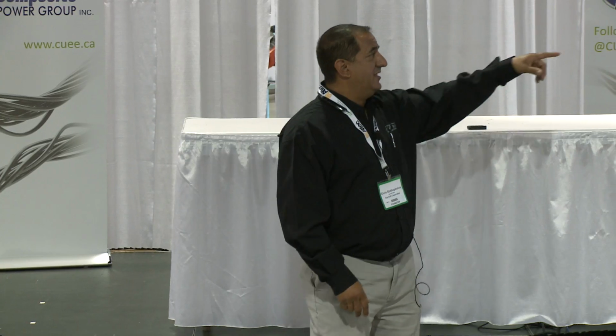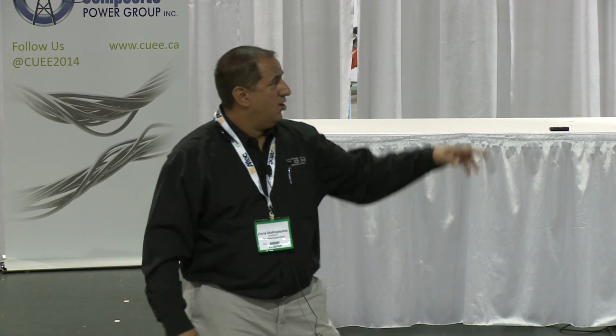Now, let's say our cable was 2,000 feet long, and it tells us right marker at open or end at 796 feet, but you open up your maps, and your map says no. The machine's wrong. The machine doesn't know what it's talking about. I know my cable's 2,000 feet. What that's going to tell me is at 796 feet, something happened. Could be a cable that's blown in two, and if the cable's blown in two, it's saying I can only see up to 796 feet. I can't see past it because our neutral's gone.